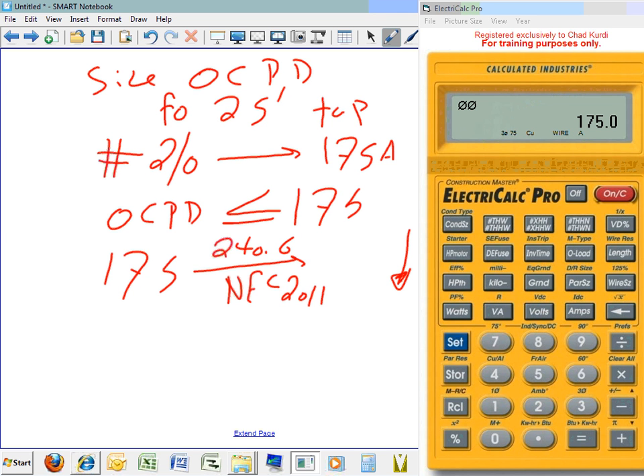Yeah, but you go back to the conductor size. Or you can go to 165 and go to the next standard up. But I always first size your conductor, then go back and see how much your conductor can carry total, right? This is how much you can carry total, right? And then based on this, you size. This will be 175 amp fuse or circuit breaker.